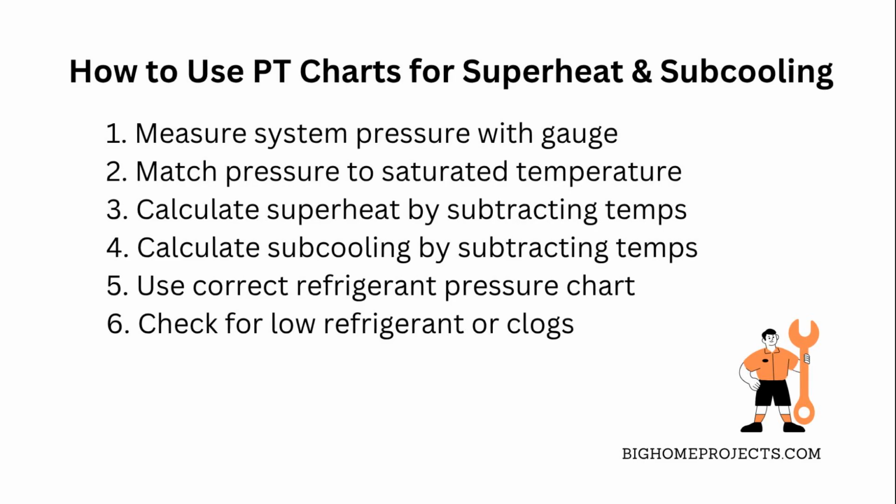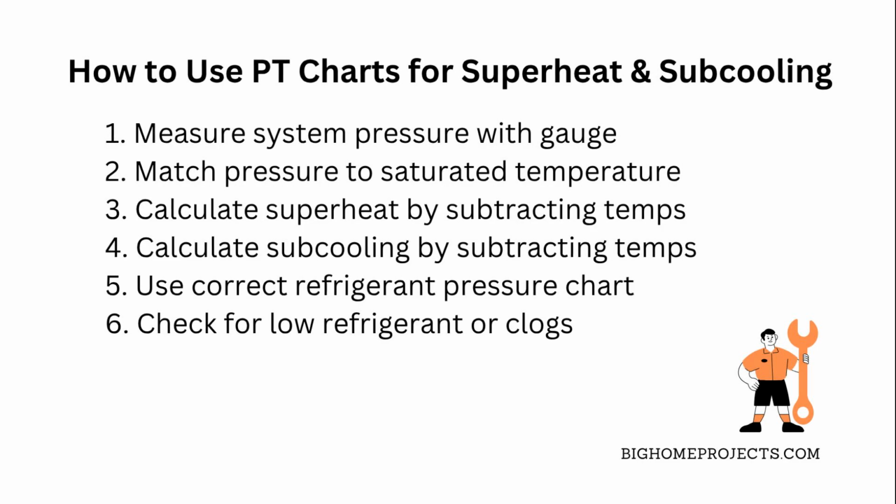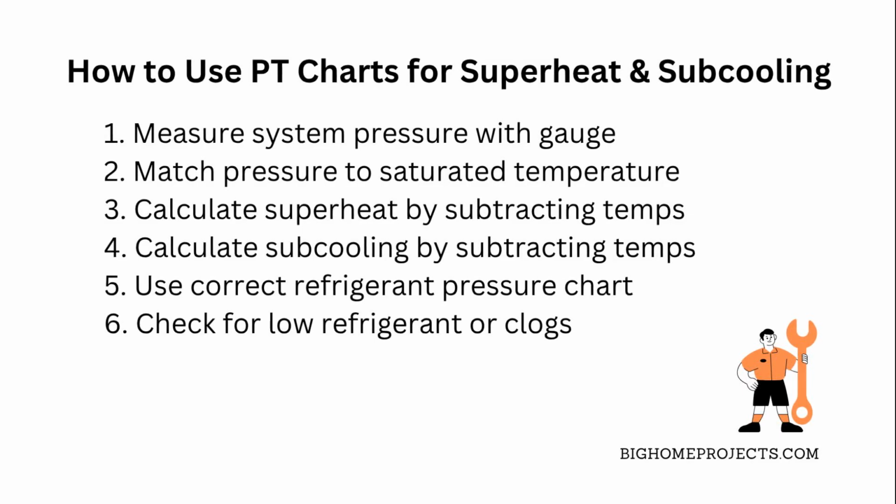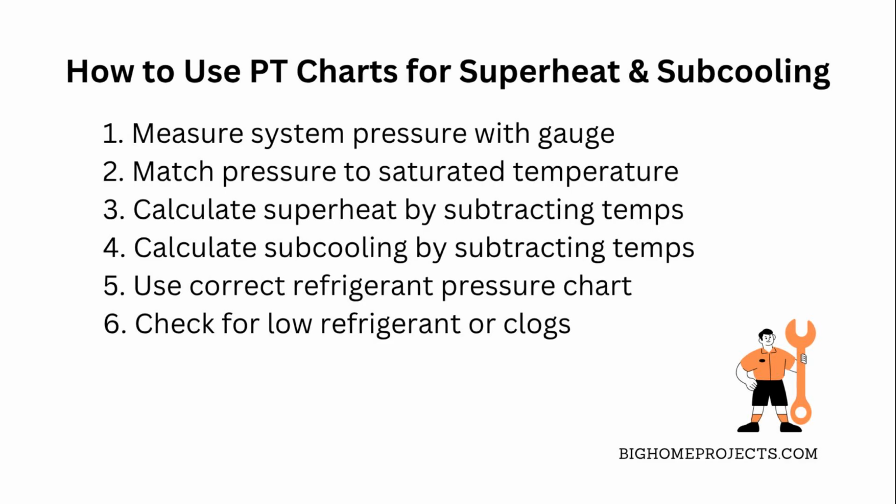For superheat, you take the actual temperature of the vapor leaving the evaporator and subtract that saturated temperature from it. This tells you how much extra heat is in the vapor after it's fully evaporated. Super important, so your compressor doesn't get damaged.